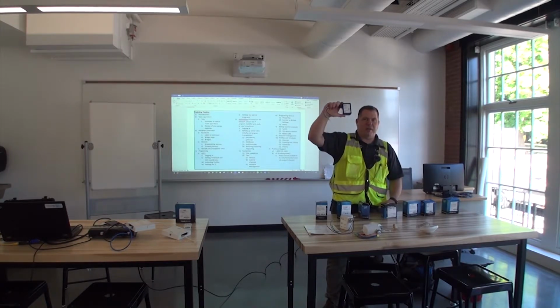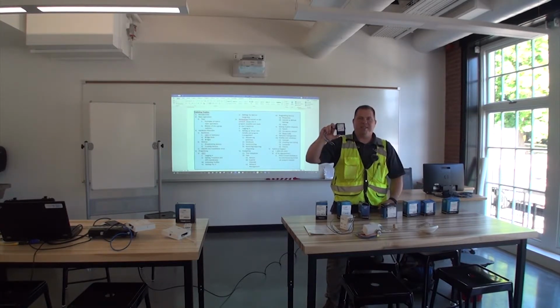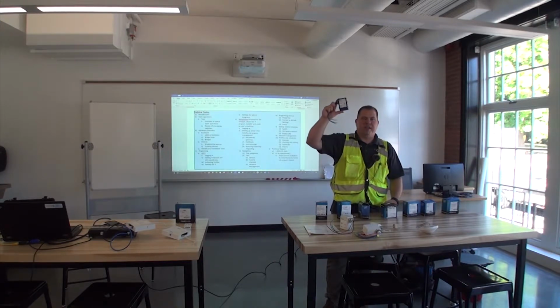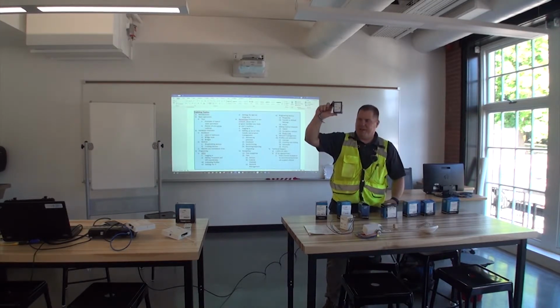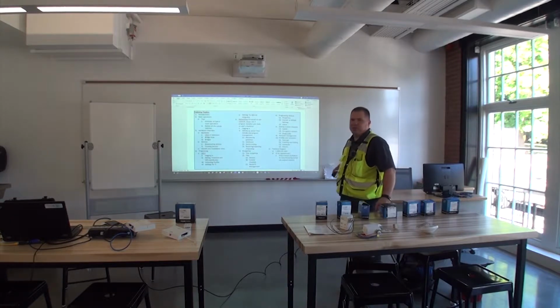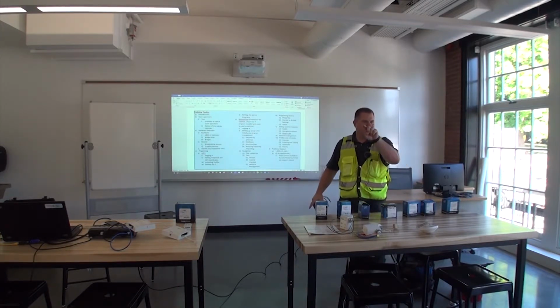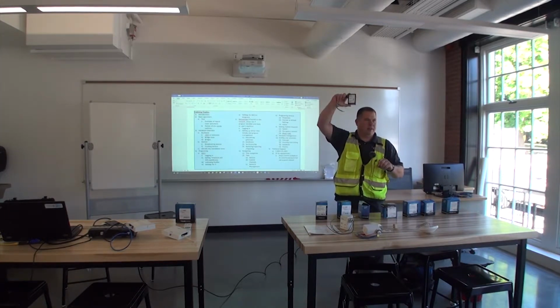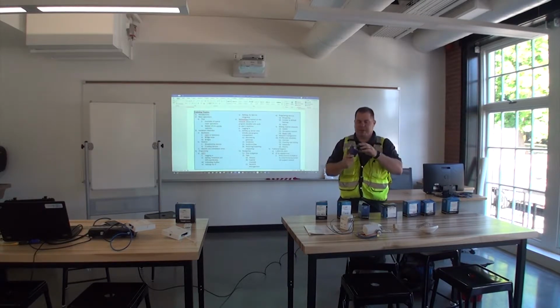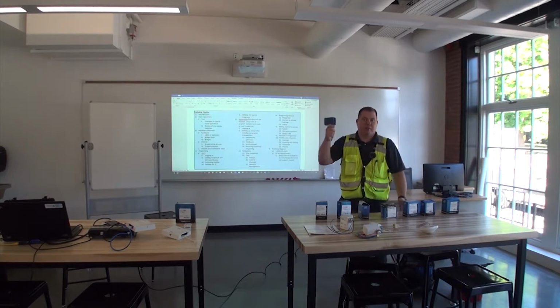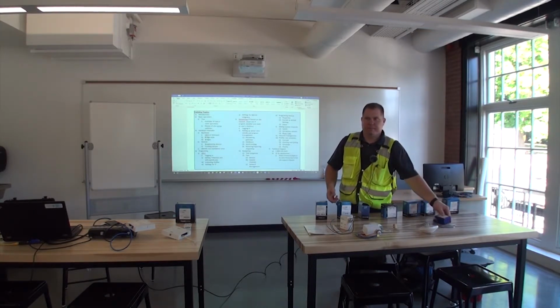This guy is a plug load device, an NPP20PL, plug load 20 amps. This is an energy code device. It plugs in so that you have a switch on the wall that's labeled controlled. If you've ever seen a plug on the wall labeled control, that's this guy right here. It just turns the circuit on and off with the occupancy sensor, and it doesn't produce bus power, because it's not a normal power pack, it's just a relay through the system to turn it on.